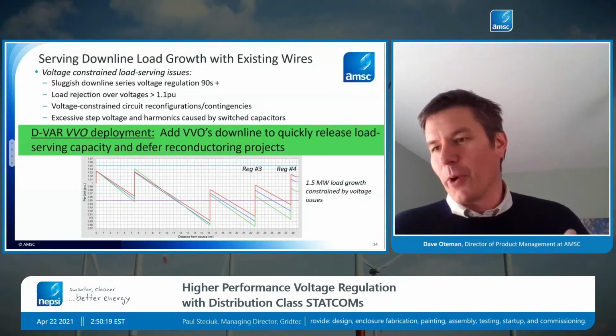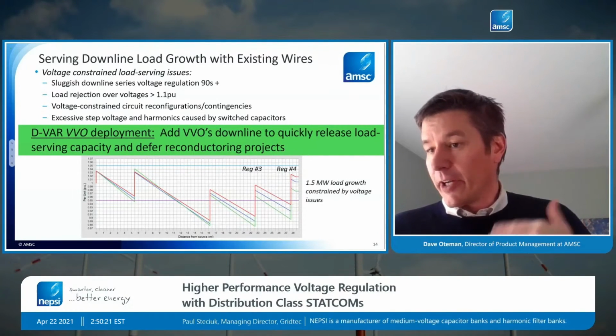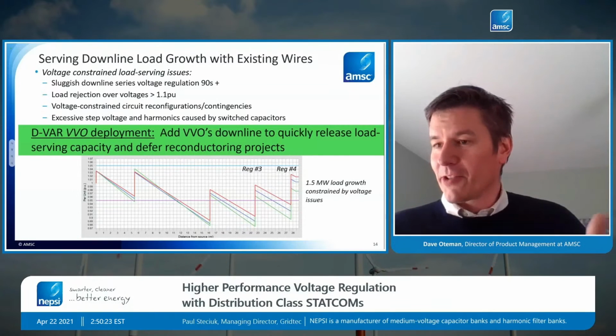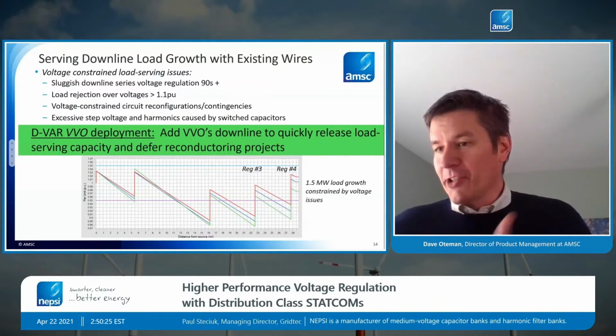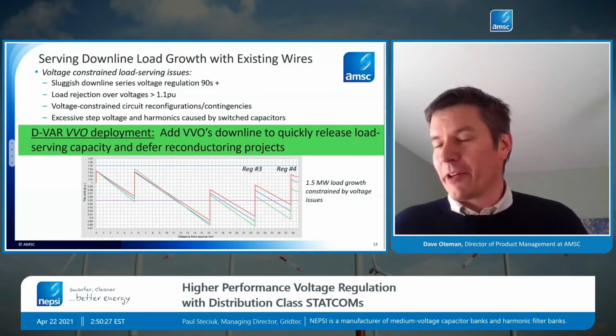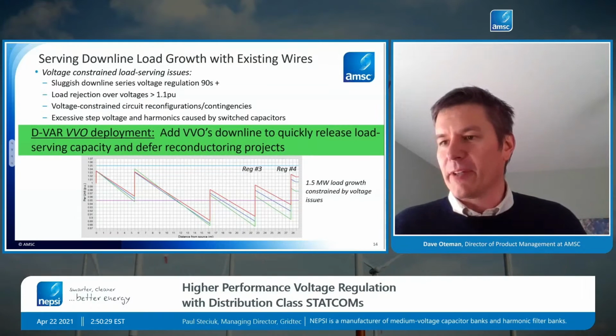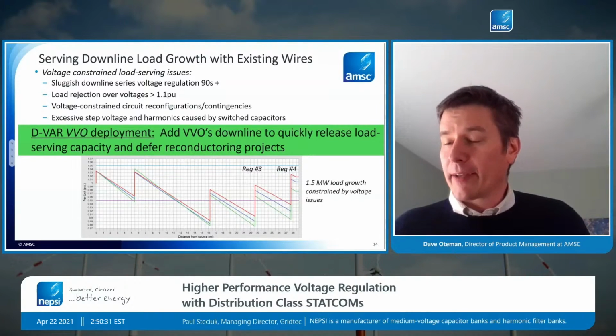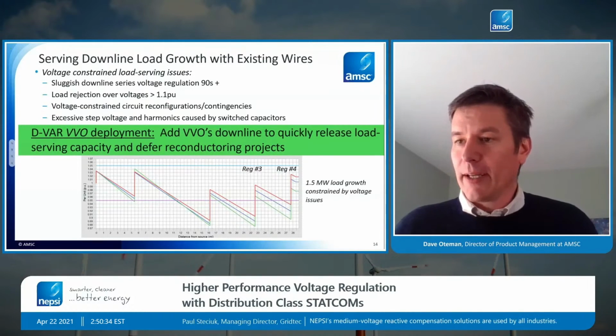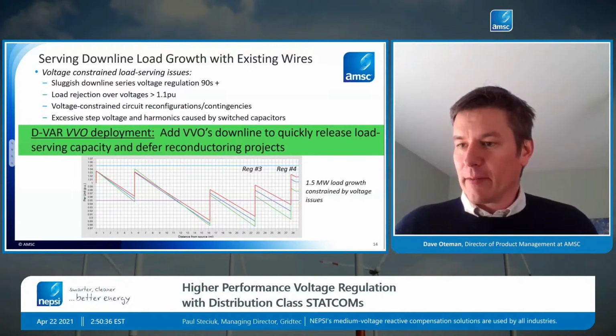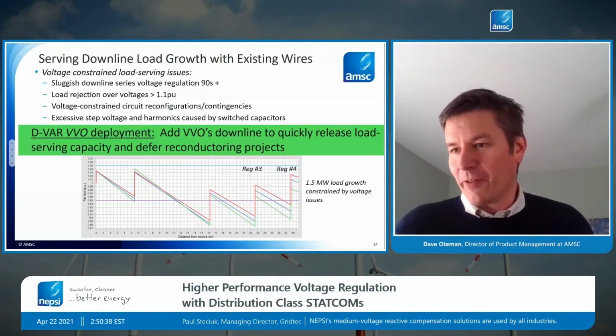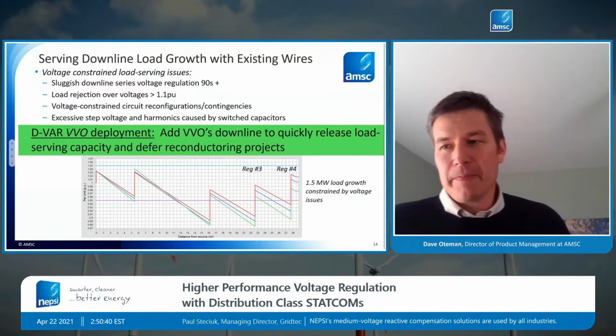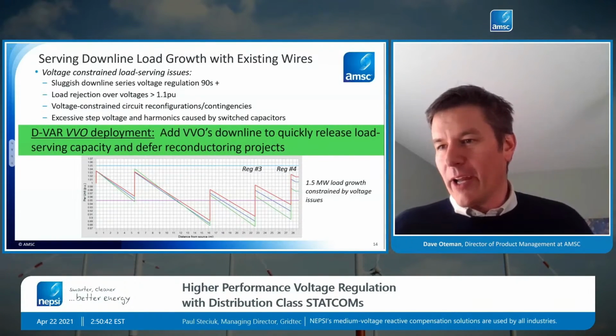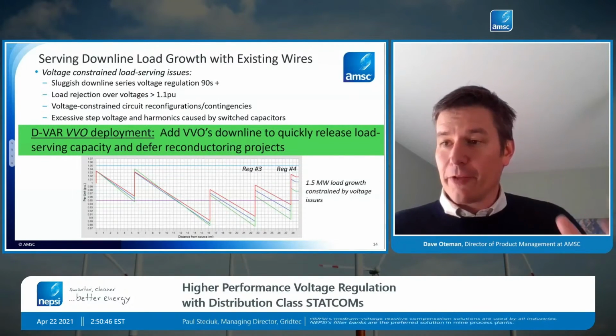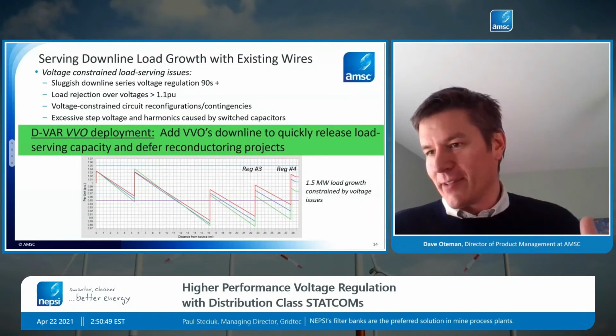So here's a case where it's very conventional. The utility wants to serve additional load, and a customer wants to expand a plant, for example, or expand for some reason. And here's a tool now that can let us very quickly install and use an apparatus-based approach to serving this additional load. Additional loads in the 1.5 to 2.5 megawatt range are pretty achievable when a voltage constraint is there.